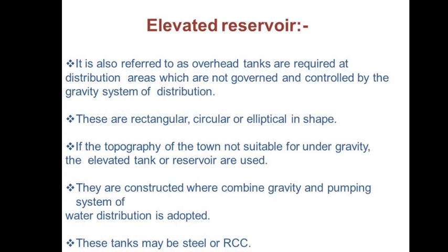Next, the elevated service reservoir or ESR, or elevated reservoir. It is also referred to as an overhead tank, required at distribution areas which are not governed and controlled by the gravity system of distribution. These are rectangular, circular or elliptical in shape. If the topography of the town is not suitable for distribution under gravity, then elevated tanks or reservoirs are used. They are constructed where a combined gravity and pumping system of water distribution is adopted. These tanks may be steel tanks or RCC tanks.